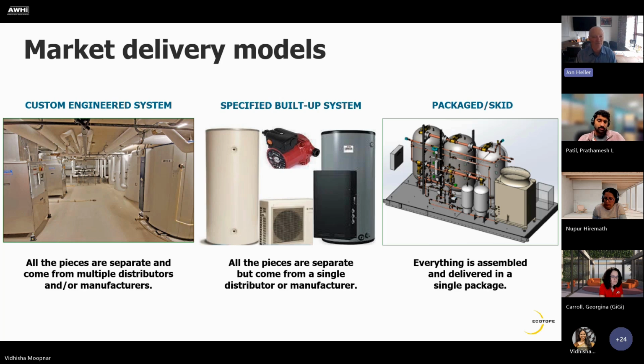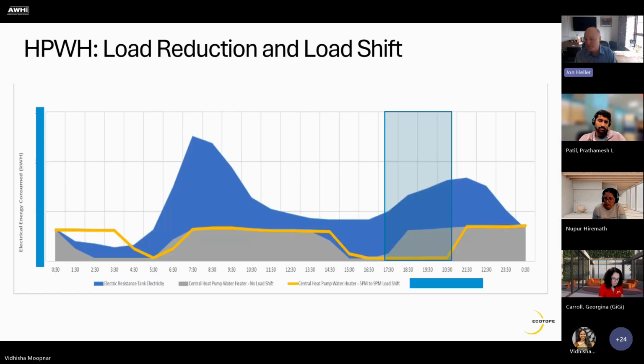The other thing I want to point out that becomes possible with these large systems is the ability to shift load off of peak utility periods. On this slide, the blue line shows a typical hot water demand load for electric resistance water heating. By shifting to a central heat pump water heating system, you get what you see in the gray bar. You've reduced the peak load by about a factor of 3, and really flattened it out over the day instead of having these big morning and afternoon peaks.